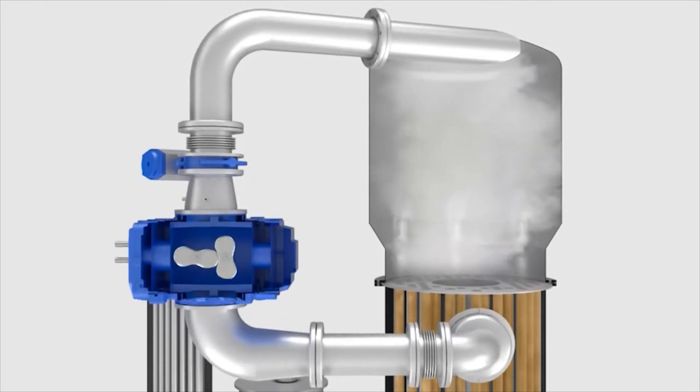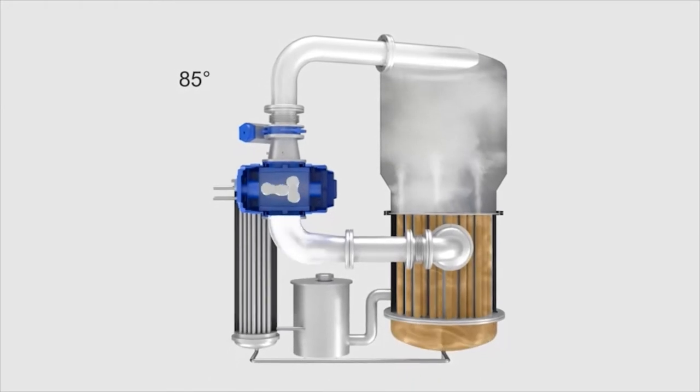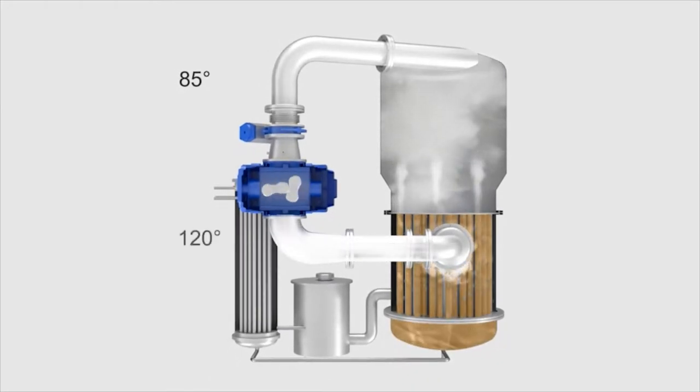The vapor compressor compresses the 85 degree hot steam, creating compression heat. Steam leaves the vapor compressor at a temperature of 120 degrees. In the bundle of pipes, hot steam meets the cooler pipes of incoming wastewater.